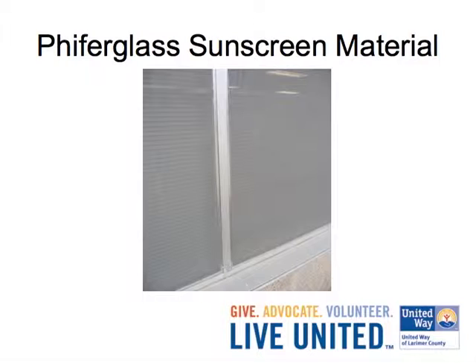However, it blocks 90% of ultraviolet. I was so excited the first day that he put in the very first screen. I took my little thermometer on the inside to measure one window with the screen, one window without the screen. It was in the winter, when the angle of the sun was down and there was a lot of solar gain happening, and it was a 10 degree difference. What that has done for their office: not only did it help us through that awkward period where we didn't have good controls and didn't have the system split out, but it reduced glare, because all this glass is not low-E glass. It reduced the glare and it gave them privacy. They can see out just fine, but people can't see in quite so much, and it's really improved operations.